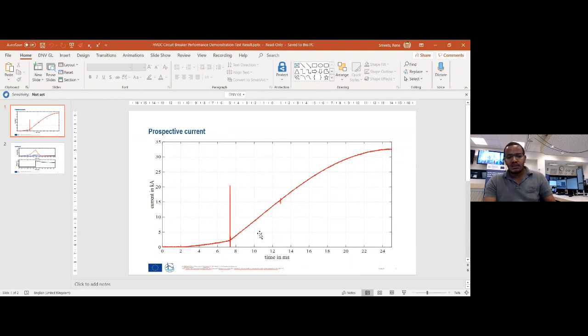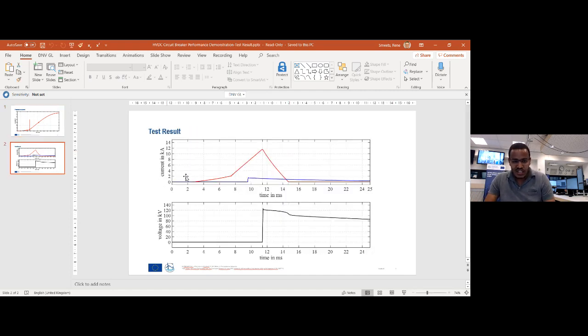What I would like to explain to you, I took a quick action to plot the results here. That was the prospective current. If the circuit breaker wouldn't be operating, the circuit current would flow like this, like what you see here, almost about 33 kA. This can only be done by a DC circuit breaker. Had it been an AC circuit breaker, it would clear later, at like 50, 60 milliseconds later. But in this case, the circuit breaker could clear.